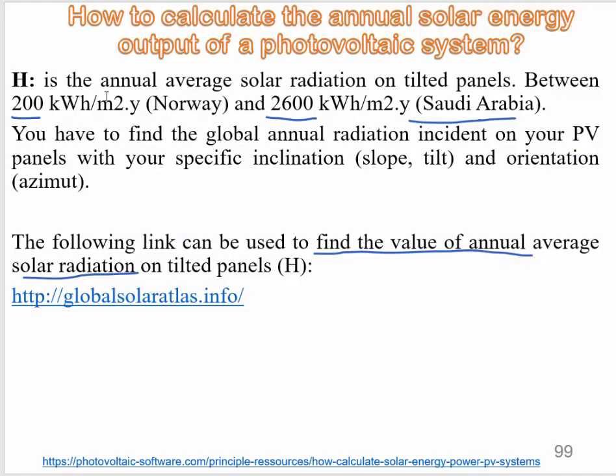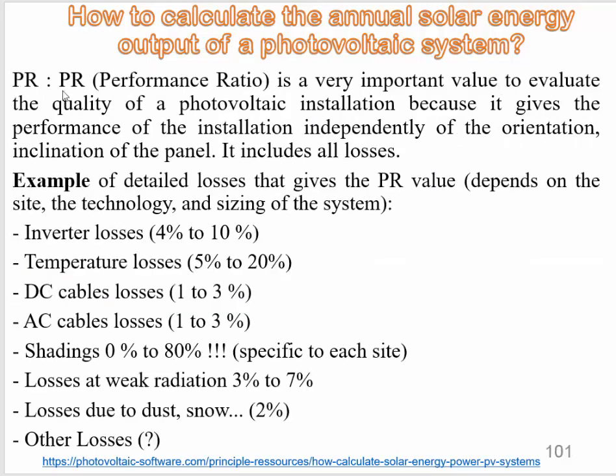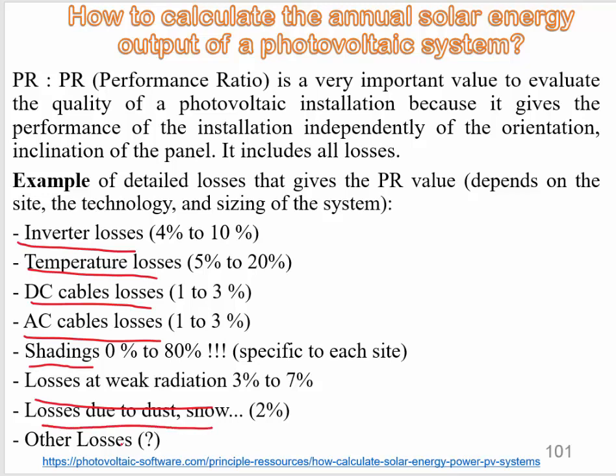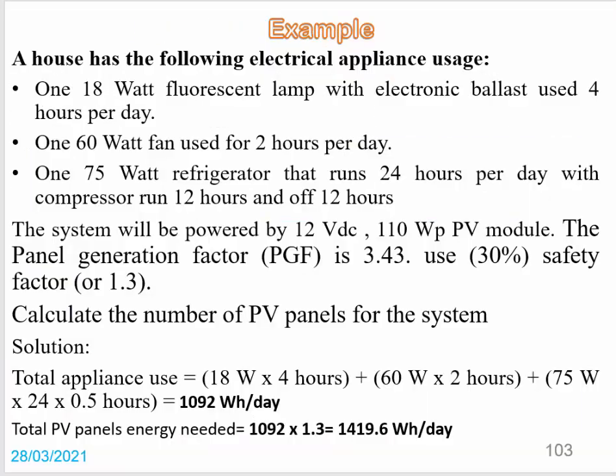From this diagram we can determine H, the annual average solar radiation. The next factor is PR, the performance ratio, which depends on losses. We have many types of losses: inverter losses, temperature losses, DC cable losses, AC cable losses, shading losses, losses at weak radiation due to dust or snow, and other losses. The most significant loss is shading.